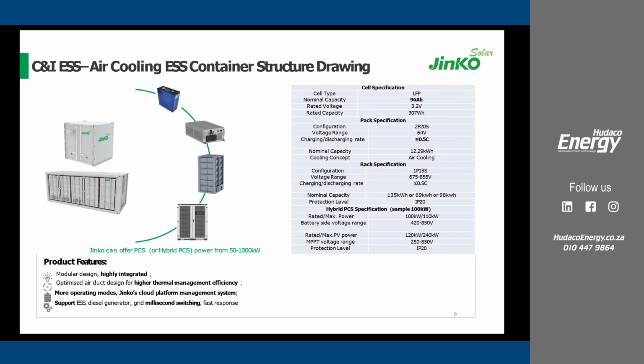The other important thing on the battery side is that we have a 3 level BMS. The lower level is the battery management units. Each of the battery packs has battery management units monitoring up to the cell level. Then on the rack level we have the second layer of the BMS, housed in the HVU, the high voltage box, responsible for getting all the data from all the BMUs and sampling it.